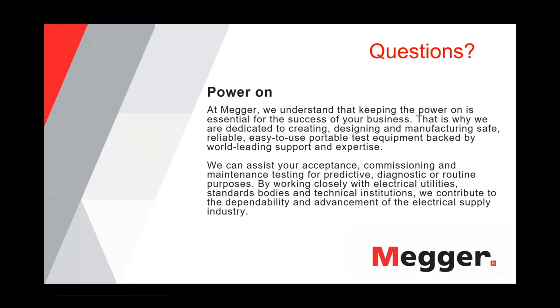And this is really an application. If you want to do hipot testing or VLF testing, then the cosine rectangular wave shape has a big advantage to offer here, because you can measure leakage current. Now, in leakage current, you have a similar issue because the leakage in paper is higher than the leakage in XLP. However, what you can do in these cables, and that's how it's done, you know the composition of this feeder or this cable.